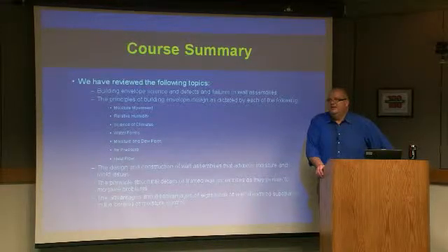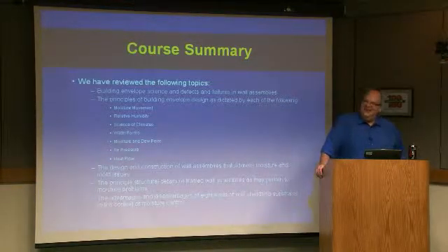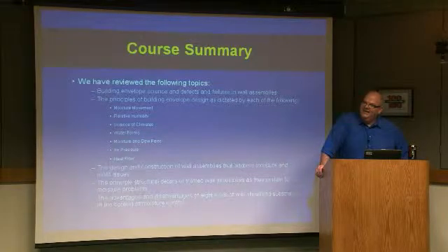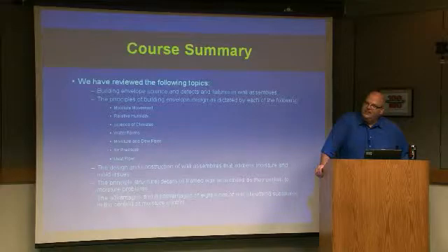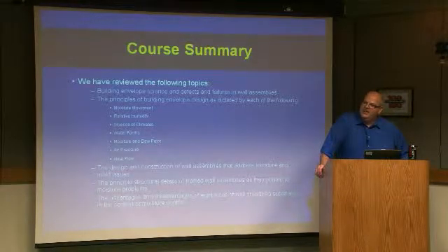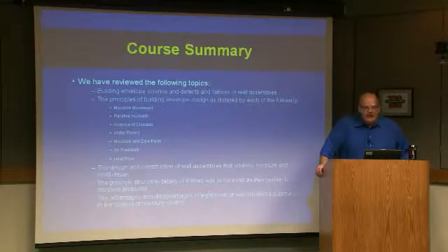I did have one more. Double vapor retarders, I know you're talking about basically from the inside to the outside. You don't want to have that because you can trap moisture inside. Right. But we've been told that you can have vapor retarders right next to each other. Yes, you can have them side by side.